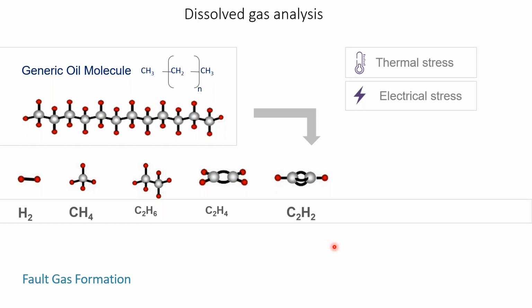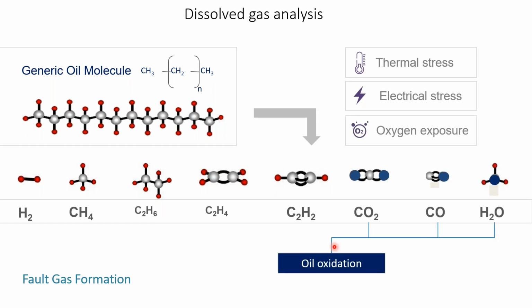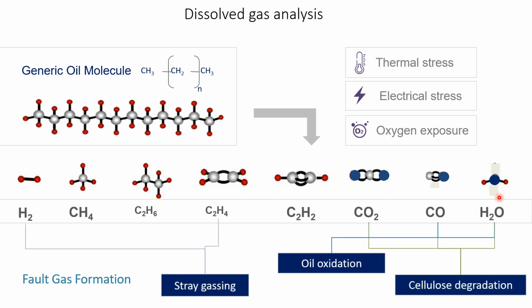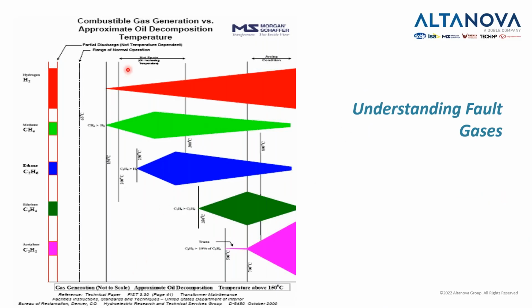conditions which you have in your transformer, you will have different gases in your transformer. So if your oil is oxidizing, also if you have an influx of a lot of oxygen, then you will have carbon monoxide, carbon dioxide, and or you will even have water in your transformer, which will show you that you have cellulose degradation. And here you can see at which temperatures which gases start to appear. So, for example, for hydrogen, as the temperature increases, you will have more hydrogen. For methane, as the temperature increases up to a certain level, the amount of methane will increase, but then it will start to decrease. So you see, this is not linear.